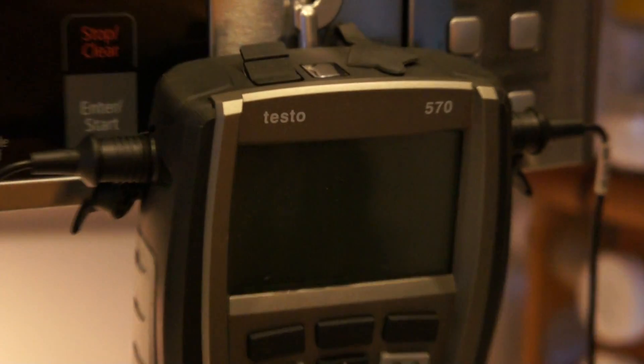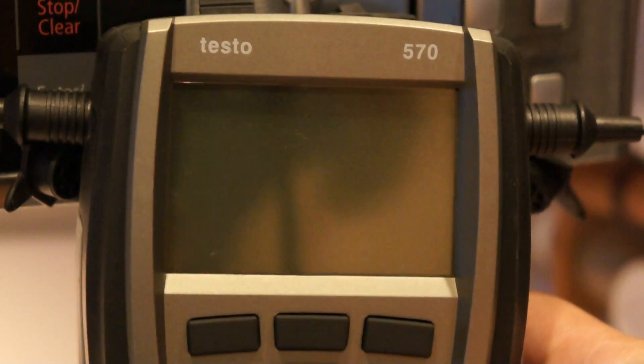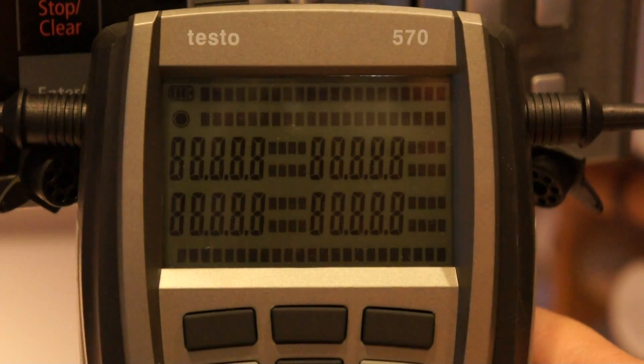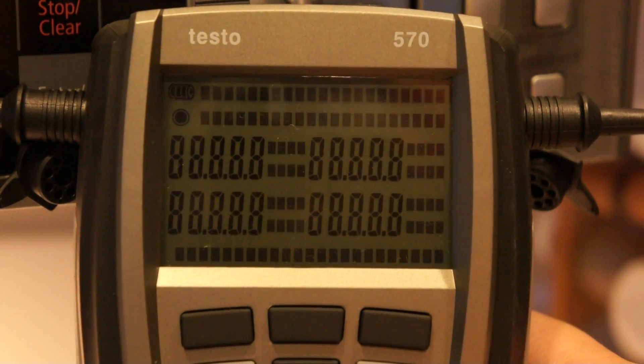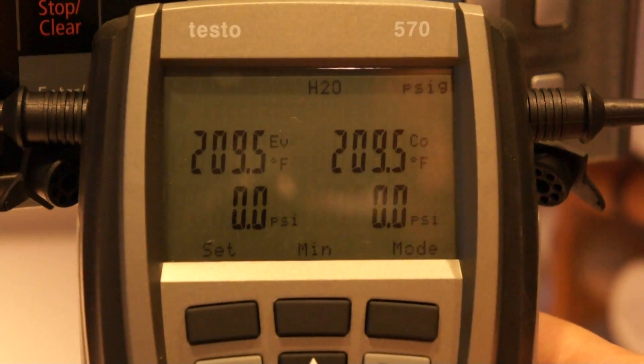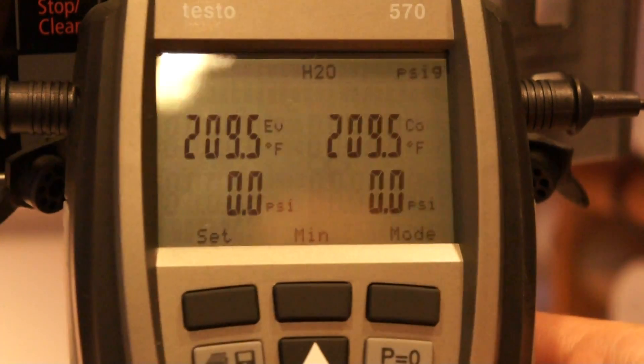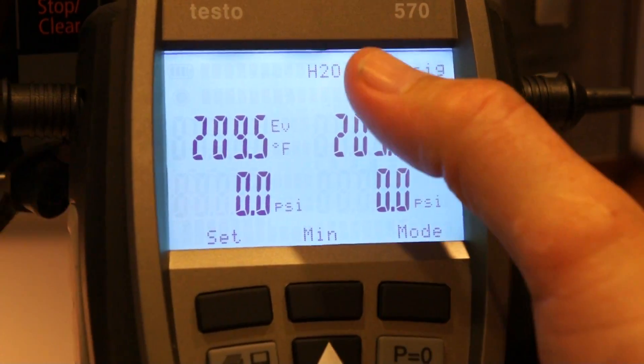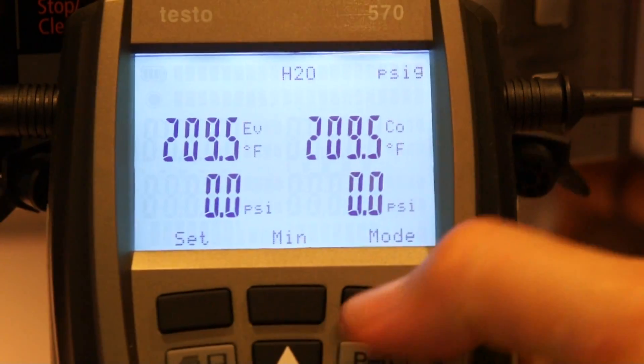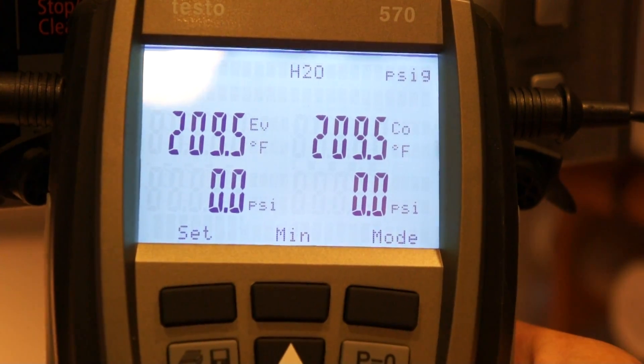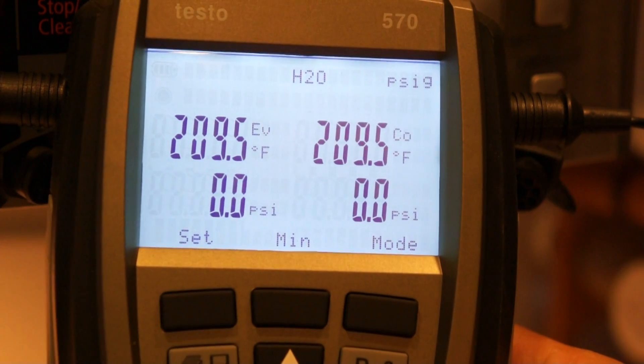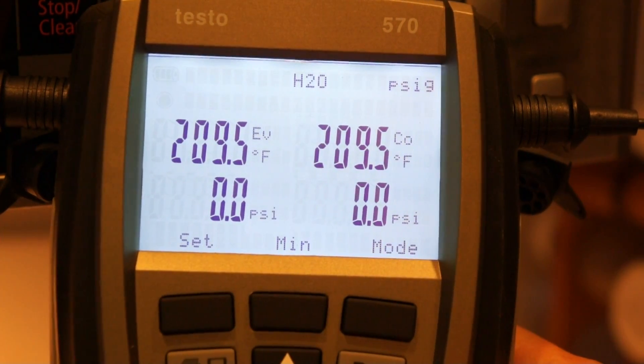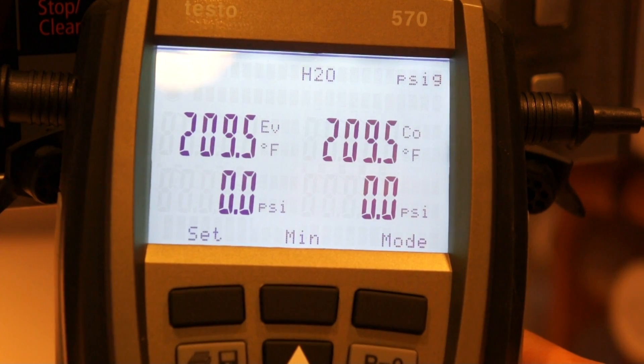I'm going to go ahead and zoom in on the instrument so you guys can see it here. I'm going to power it up. When you power up a 570 it actually goes through an internal configuration and it looks at the atmospheric pressure. So when we power it up, you can see, turn on the backlight here, that we have refrigerants that is water and it says that boiling and condensing is 209.5, not 212, and that's because we're at 1,062 feet above sea level and that changes the boiling point of water.